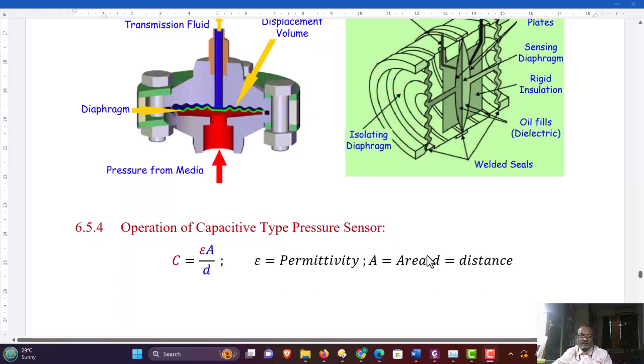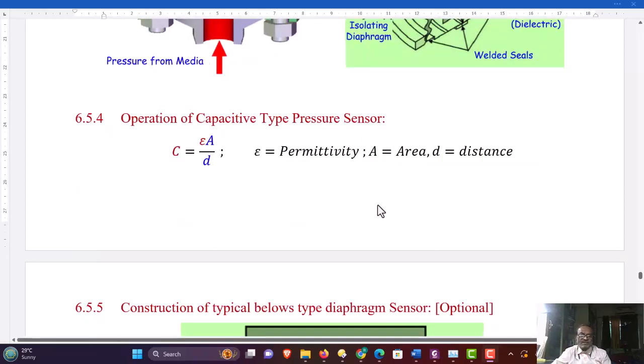For the sake of simplicity, this part can be skipped from your syllabus point of view. The operation of a capacitive transducer can be explained by the relation of capacitance of a parallel plate capacitor. We know the capacitance of a parallel plate capacitor is given by epsilon A by D. Epsilon is the permittivity, A is the area of the plate, and D is the distance of separation. So whenever pressure is applied to the measuring diaphragm, the distance between the fixed plate and the movable diaphragm changes, and therefore the capacitance changes, which is in turn proportional to the applied pressure.